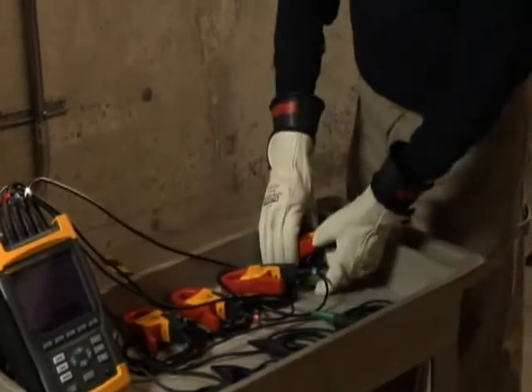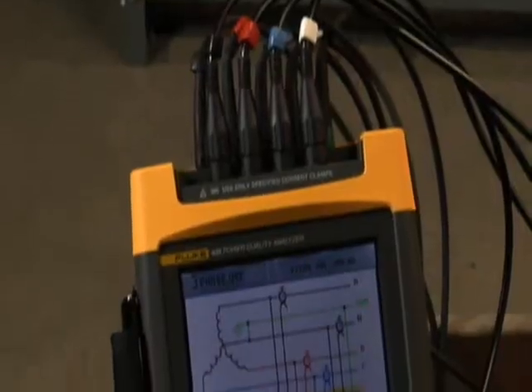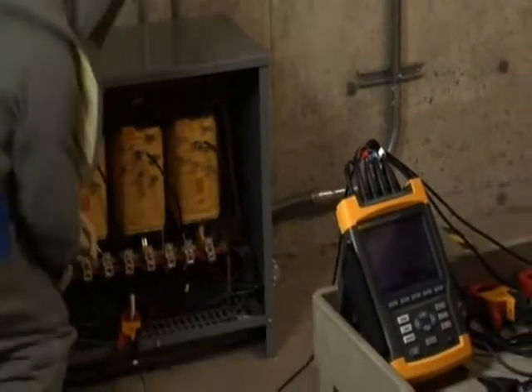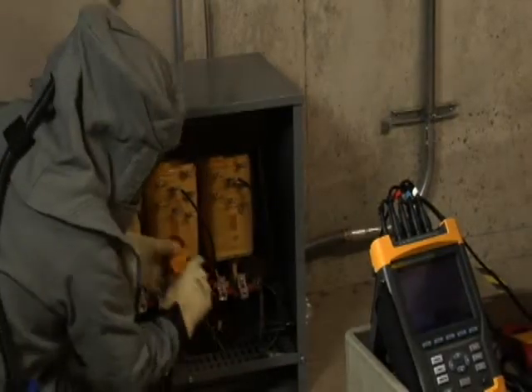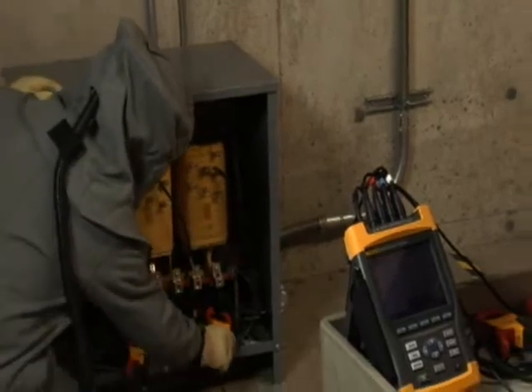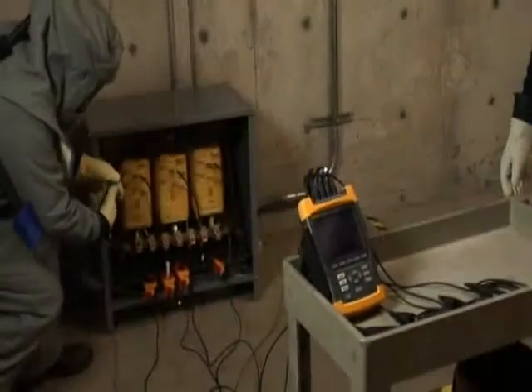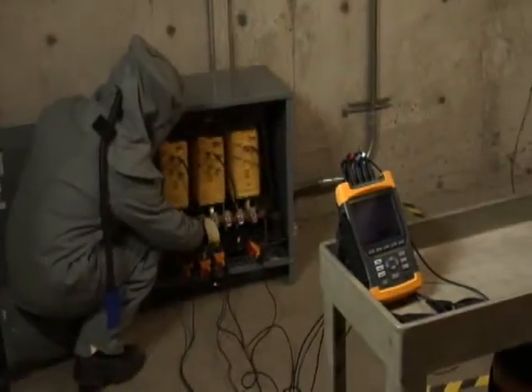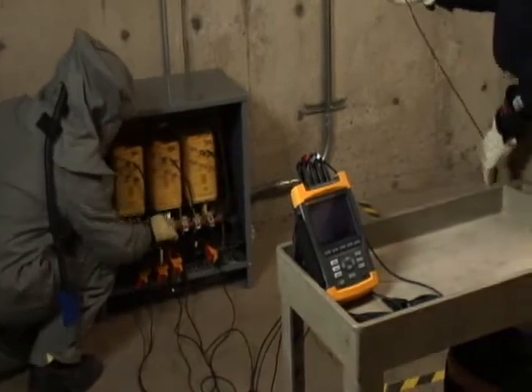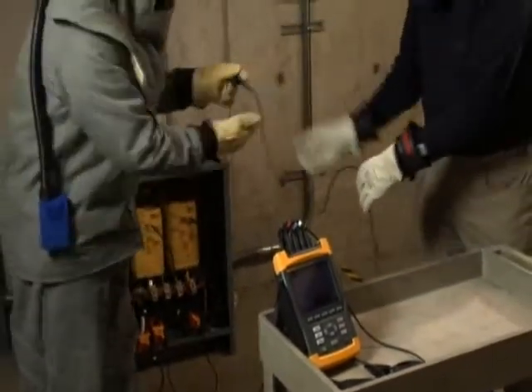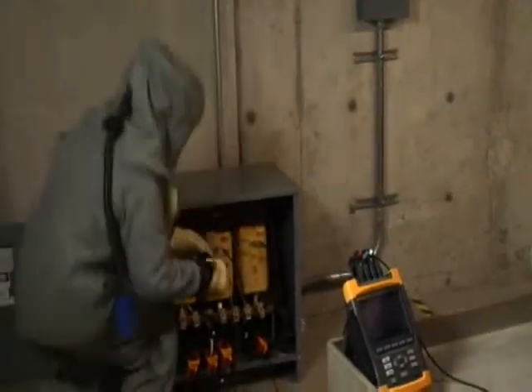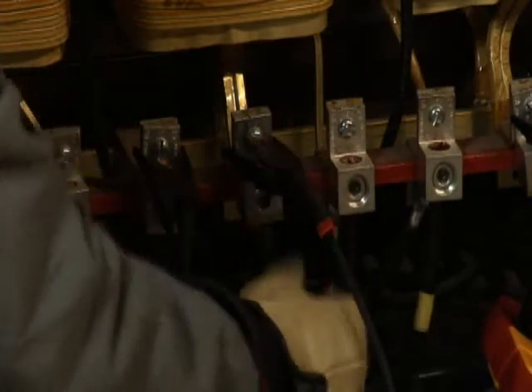Before connecting your Fluke 435 Power Quality Analyzer, make sure you have selected the correct distribution system. When connecting the Power Quality Analyzer, be sure to follow the color coding scheme on the View Configuration screen. For example, in a typical 208Y 120 volt system, we use black for phase A, red for phase B, blue for phase C, and white for the neutral. When connecting the current clamps, make sure the arrow on the clamp points towards the load. When connecting the voltage leads, make sure to always connect the ground lead first for safety. Then, connect the remainder of the voltage leads. Following the correct color coding scheme greatly reduces the chances of connection errors.